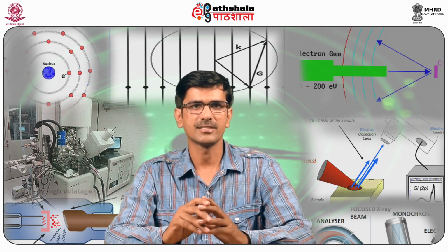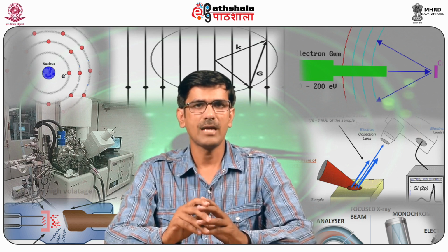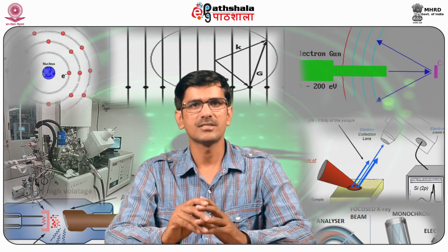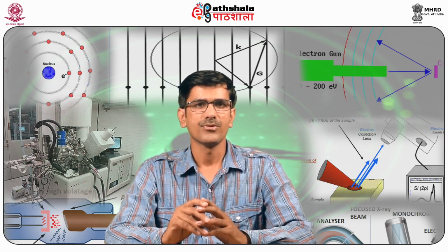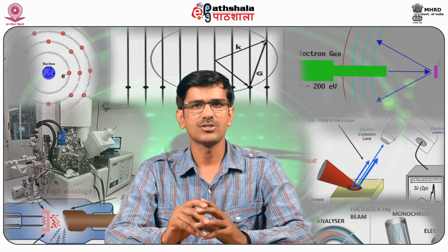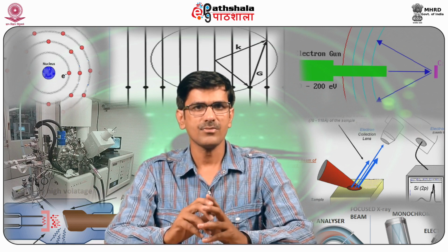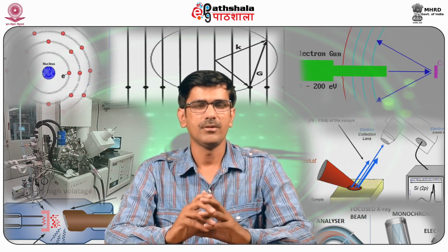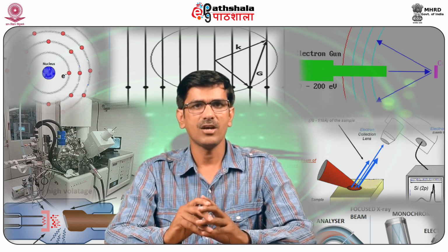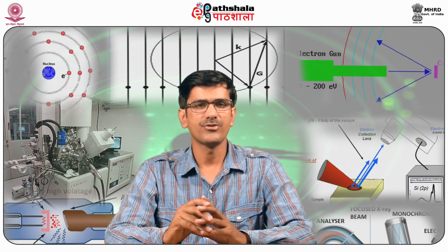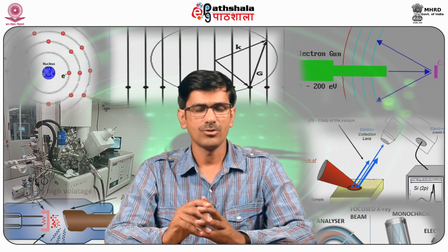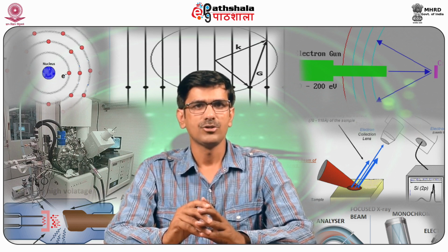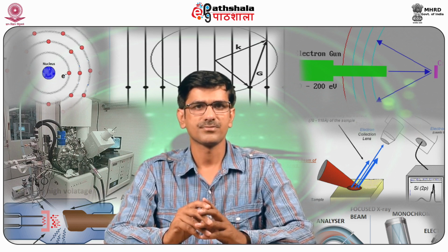for quality analysis. One of the most common types of X-ray diffraction goniometers used today is known as a kappa goniometer, which characteristically consists of 4 circles and provides 3 angles of rotation for the crystal sample. One of these angles allows the sample holder components of the goniometer to swing out, which makes it easier for the operator to mount the crystal samples.